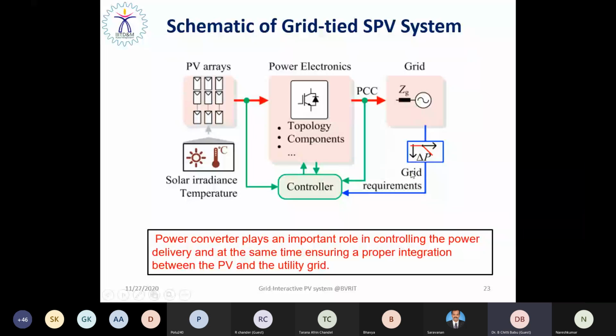That includes controllable active and reactive power, improved power quality, grid synchronization, and excellent transient response. So all these requirements are going to be met by a suitable controller on these power electronics converters, right? Moreover, it also contributes to maximum power point tracking: the input energy is light energy, so as solar irradiation and temperature vary, the output power is variable, so we need a converter to provide controllable power to the utility grid, right? So these power converters play an important role in controlling the power delivery, and at the same time ensure proper integration between the solar PV system and the utility grid.